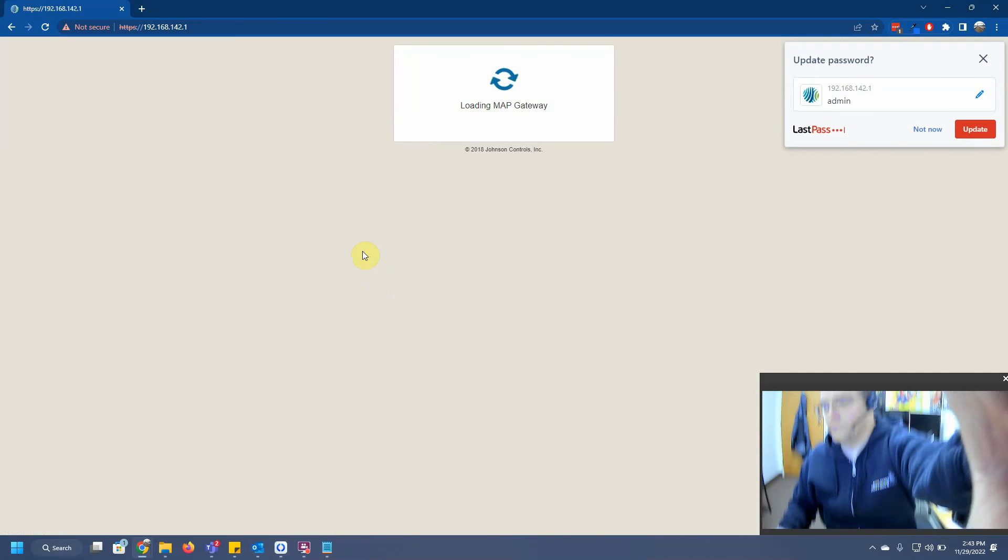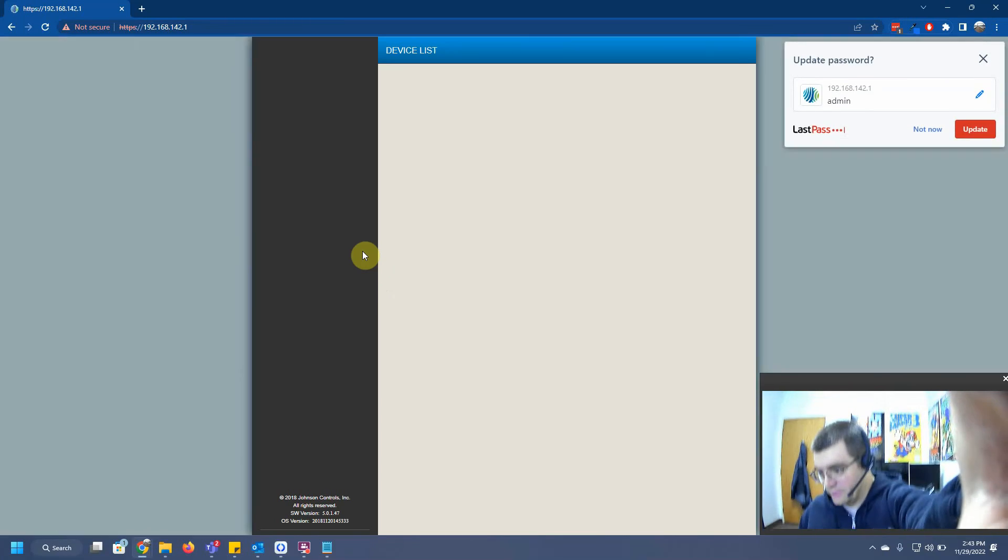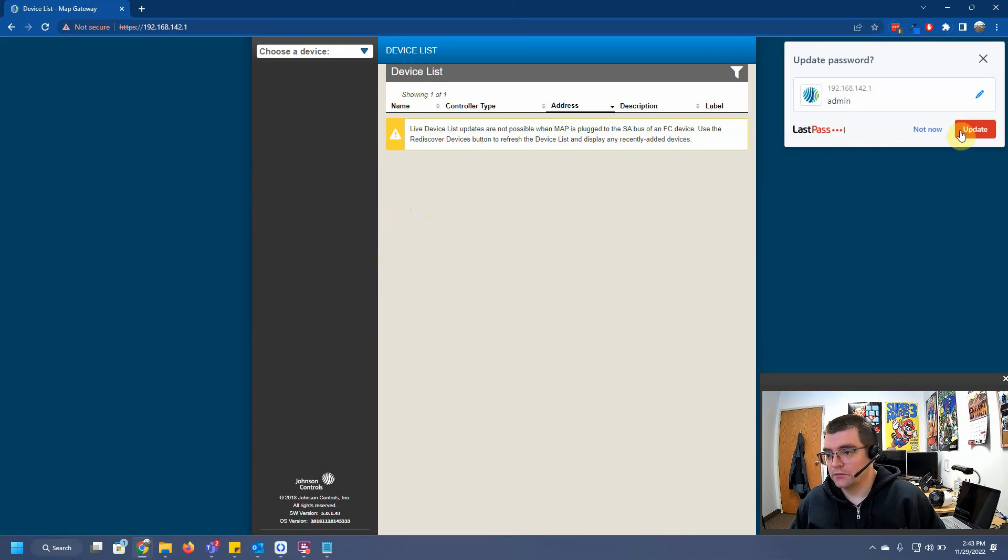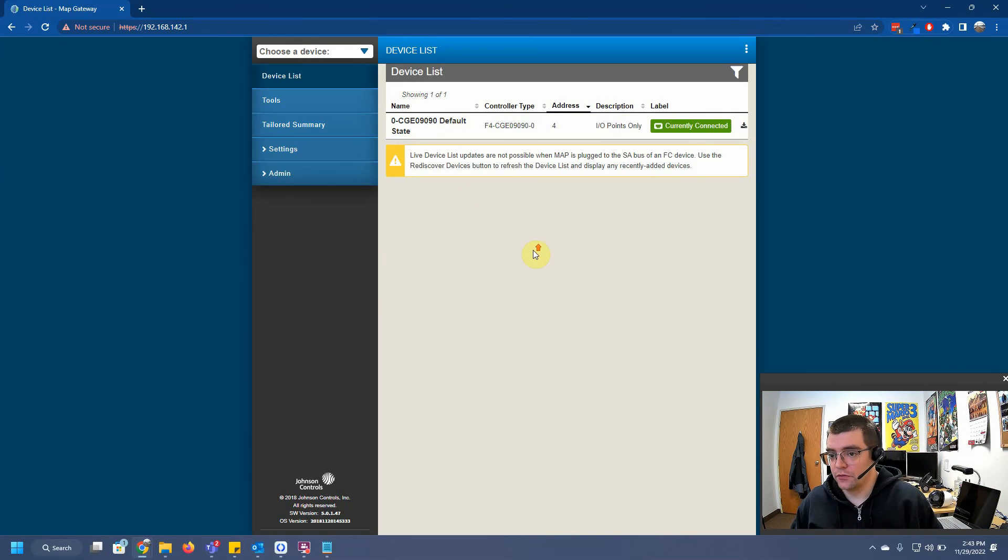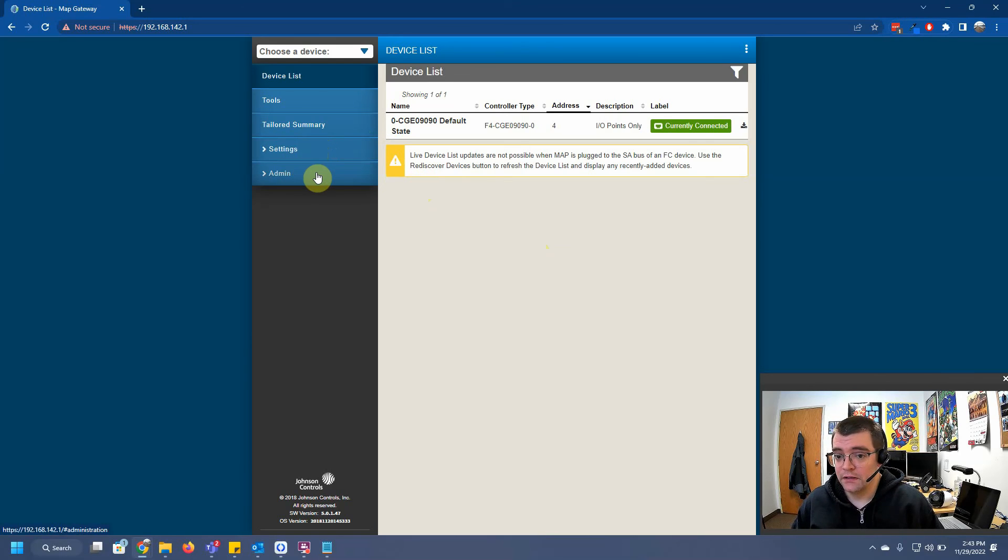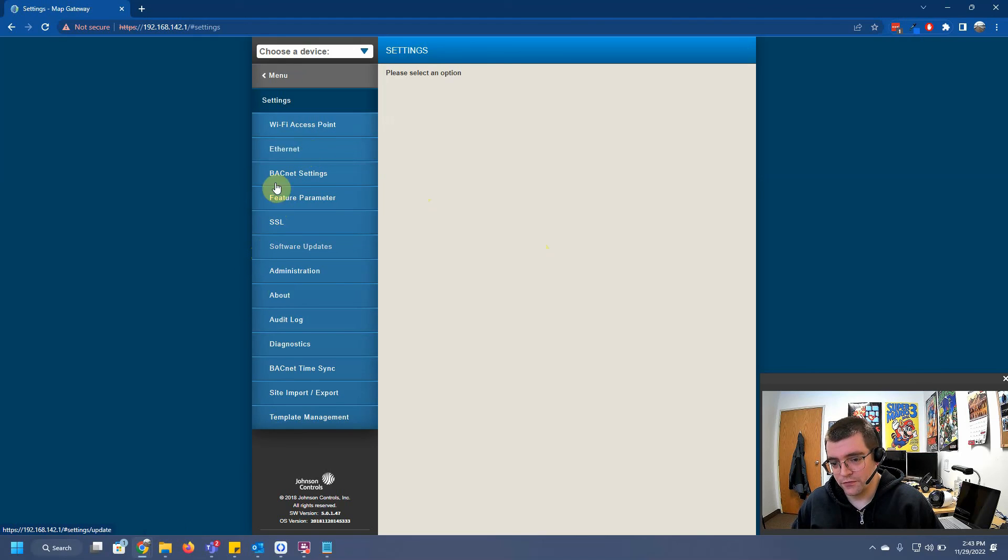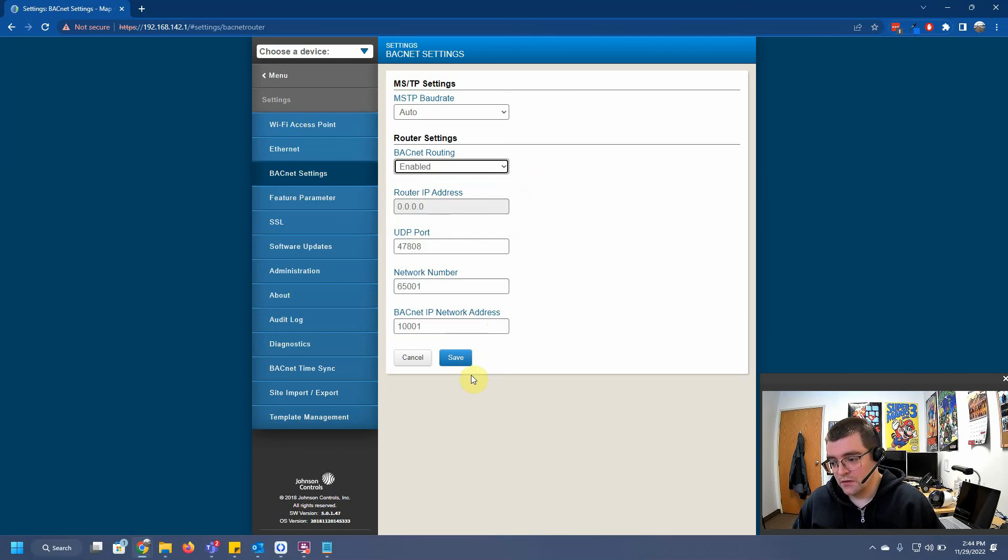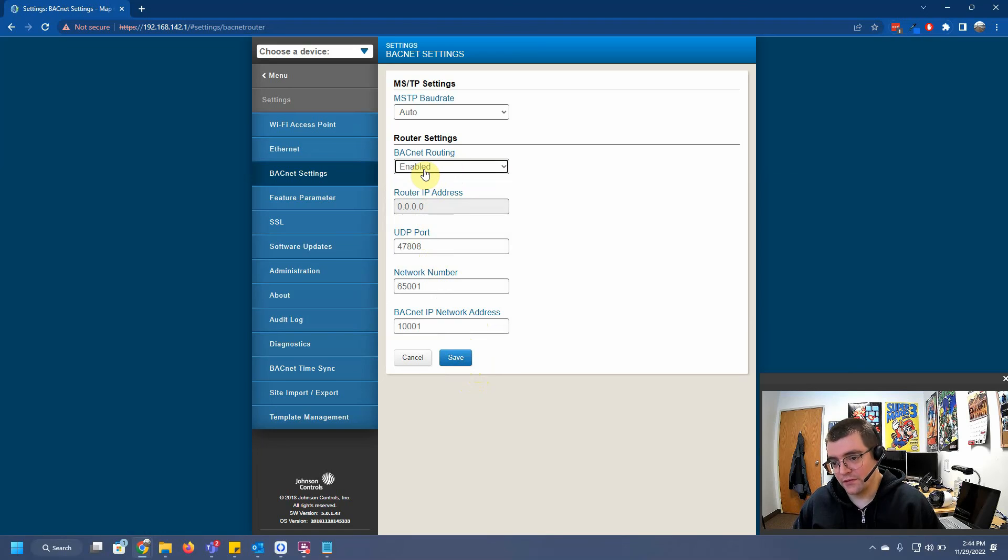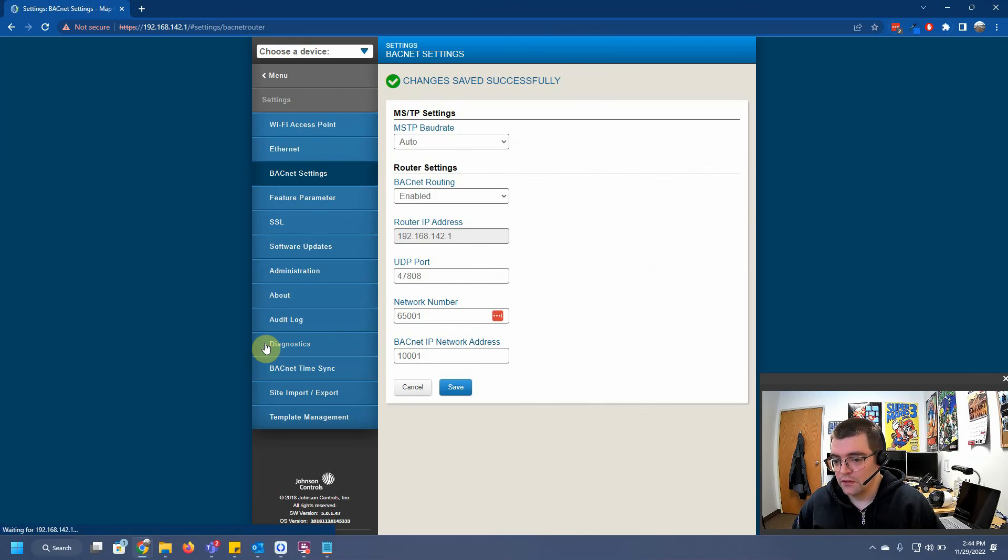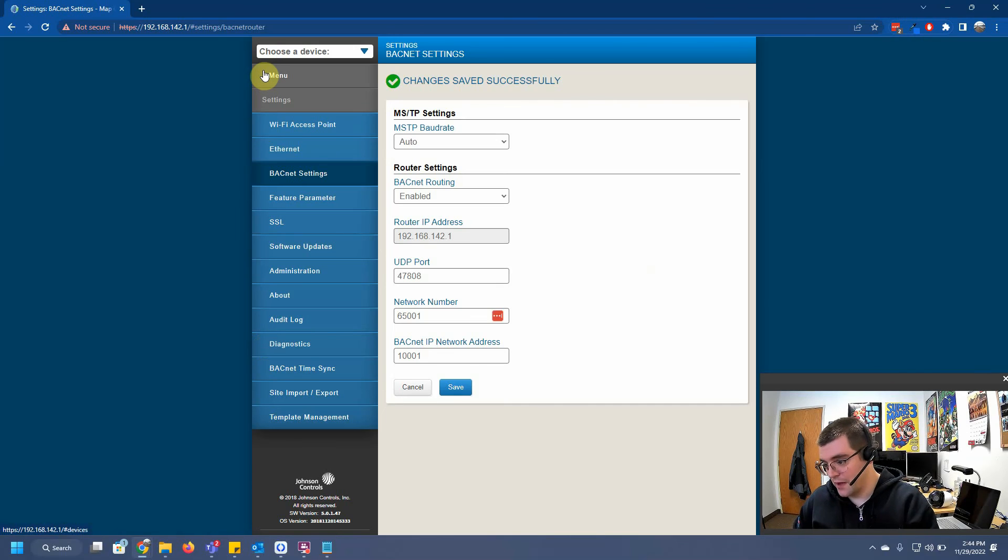And there we are. This controller is back up and running. Or this gateway is back up and running. So don't forget about this. You have to go to your BACnet settings and make sure you change your BACnet routing to enabled so you can actually program your controllers with CCT. I don't know why they disable this by default, but if you don't enable this, you won't be able to connect your devices with CCT. We're going to go ahead and hit save there. And basically, that's it. Your MAP is back up and running.